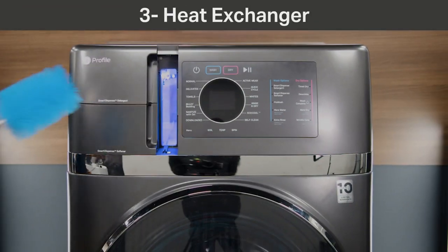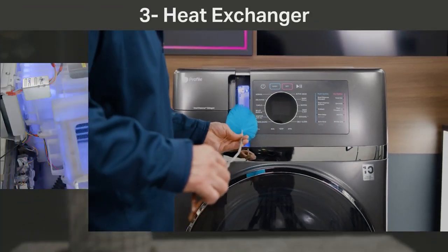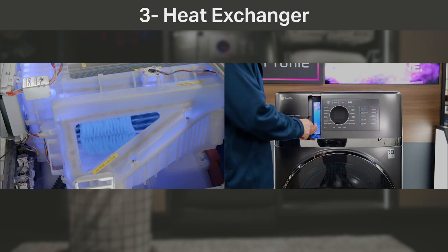The last area that should be cleaned is the heat exchanger. Any accumulated lint on the fins can be easily brushed off by moving the brush up and down, and by also spinning the brush.